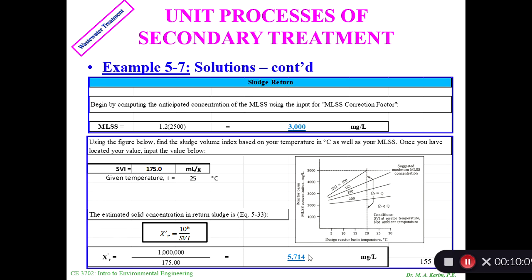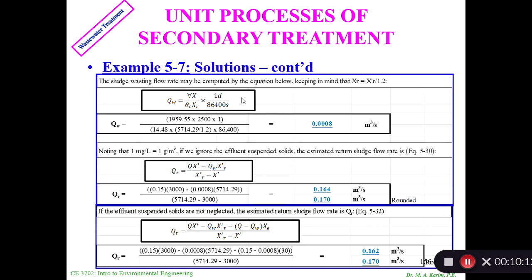This is the recirculation part, so that's fine. Then we can calculate Qw wasting amount using this equation. Qw I get 0.0008 m³/s. Then if we consider Xe as negligible, we use this equation and we come up with 0.16 for Qr. If we don't consider Xe as negligible, we use this equation to calculate the value of Qr. We get 0.162, basically the same. That means the value of Xe is kind of negligible here.